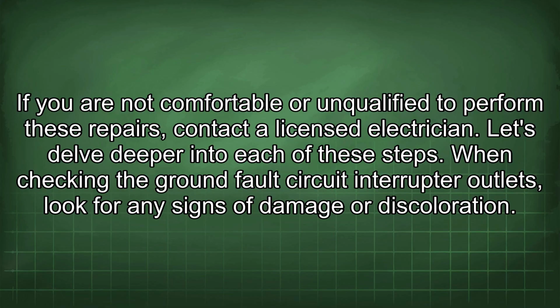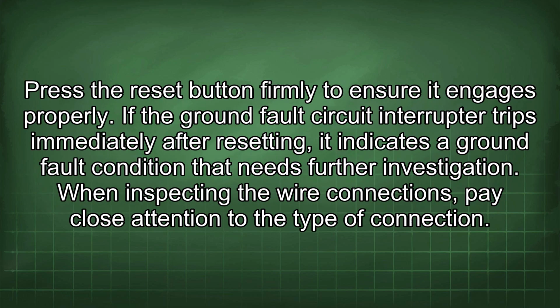When checking the ground fault circuit interrupter outlets, look for any signs of damage or discoloration. Press the reset button firmly to ensure it engages properly. If the ground fault circuit interrupter trips immediately after resetting, it indicates a ground fault condition that needs further investigation.